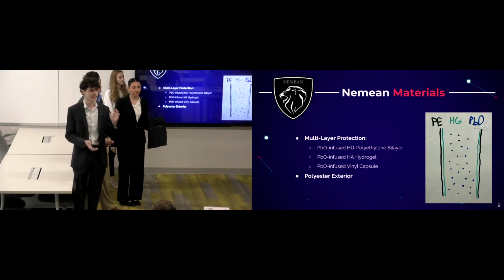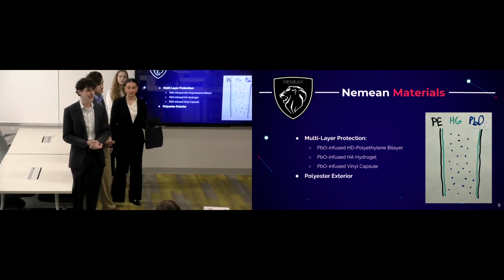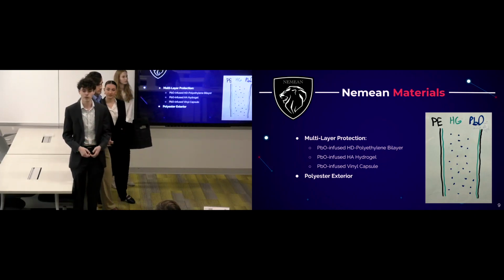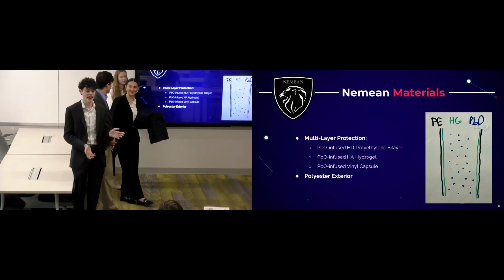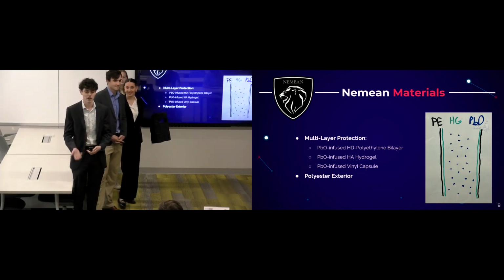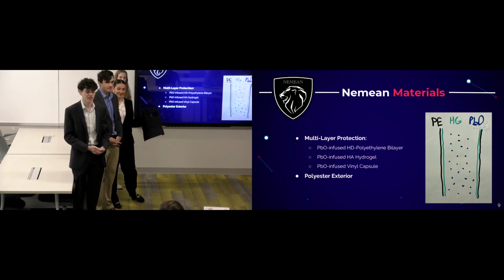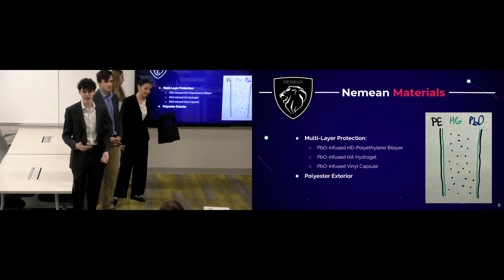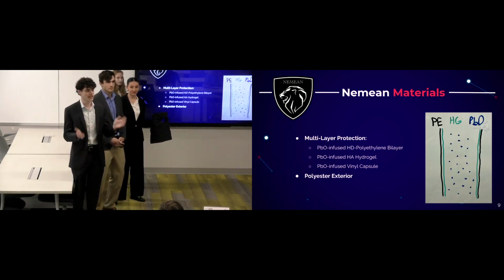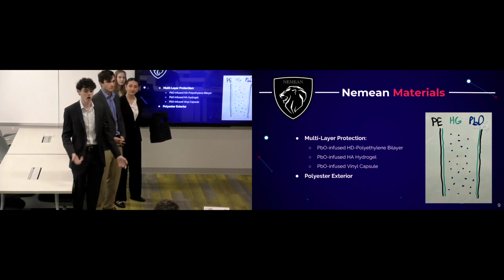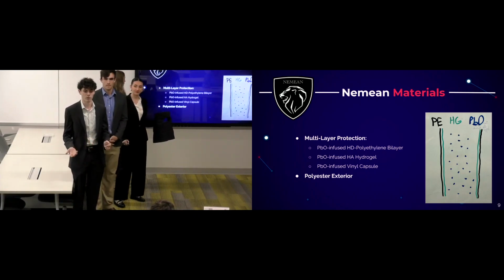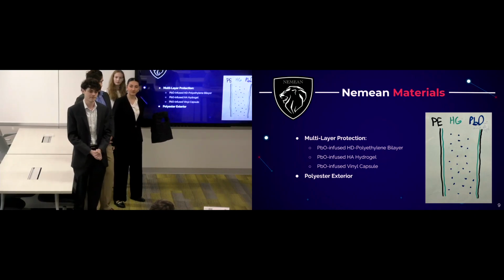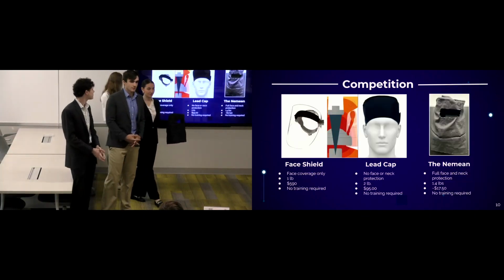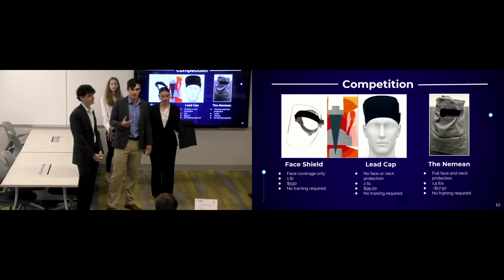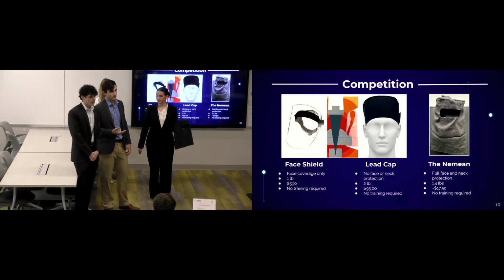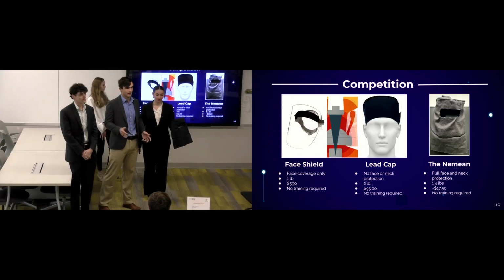Finally, surrounding both the polyethylene and the hydrogel is a lead oxide infused vinyl capsule. The point of this capsule is to form an airtight barrier around it, so that the hydrogel doesn't dry out, and we can contain the water within this, so that we don't lose those water radiation resistant properties. And again, the entire Nemean is surrounded in polyester, so that it provides comfort to our physicians and can be easily cleaned. So although there are current solutions that protect the head from radiation, like the Zero Gravity from Biotronik, they're exorbitantly expensive and they are not available to your average physician.